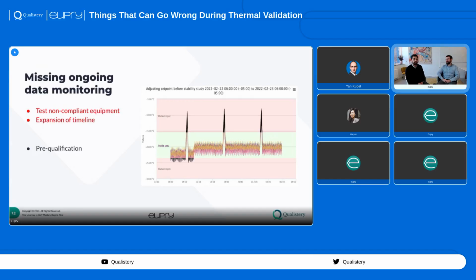And so what can you do? Well, the pre-qualification is basically much easier when having a monitoring of your data while you start off everything. So what's pre-qualification? That's basically doing some data gathering and looking at the data and seeing if everything is all right, that we can go ahead and everything looks good. Because it could be some simple issues such as having too low of a set point. The graph you see on the screen depicts a situation where a freezer is actually a bit too cold. It's low, beyond the lower limit. And then with a slight change, it looks pretty well afterwards. So that's the pre-qualification, and it's only possible and easy when you have data monitoring. So that's a thing. And then generally you can act upon issues immediately.